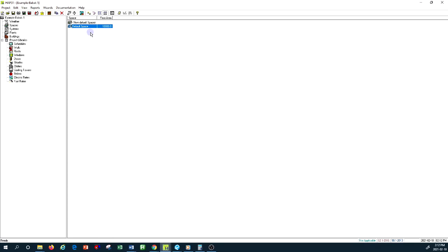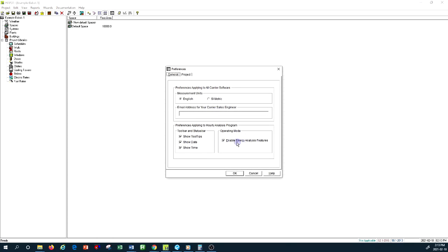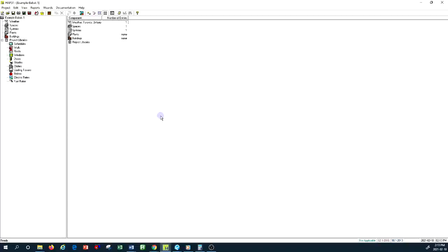So I've determined the schedule based on the mode of operation on the software side. It's very important to know which mode you're working in: if you are in Energy Analysis mode you can assign different schedules to all days of the week, but if you're in System Design mode the software automatically assumes all your loads are in place and designs cooling based on your maximum peak load.